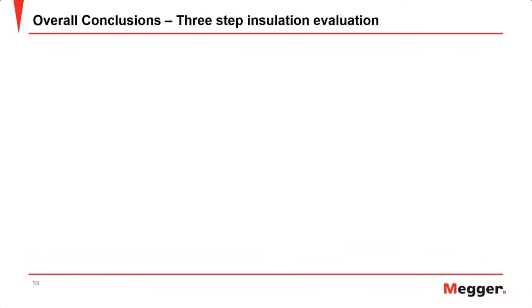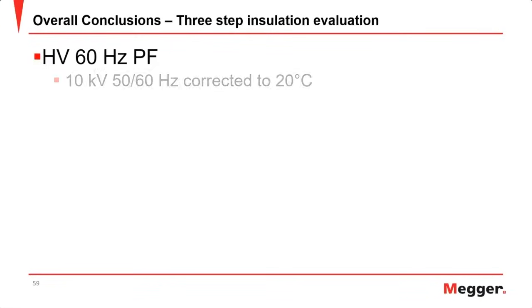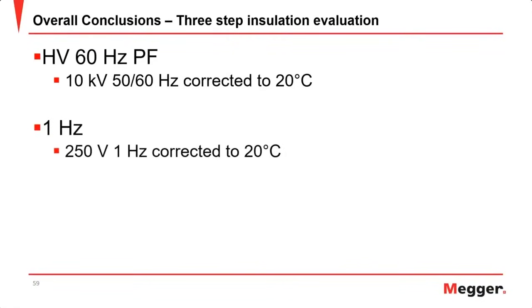You're going to do your high voltage 60 hertz power factor. You're going to take that 10 kV measurement and you're going to correct to 20 degrees C using ITC measurements. You're also going to look at the 1 Hertz. This is a lower voltage test, and again, reducing voltage should not change your power factor measurement for OIP systems.